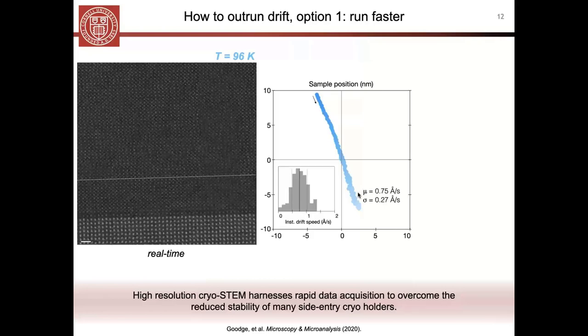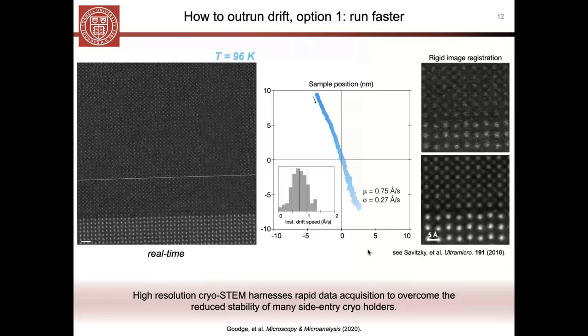Now, for very fast imaging techniques, or relatively fast imaging techniques like in particular high resolution TEM or high resolution STEM, one way around this drift is to acquire a series of very fast images - a stack of fast acquisitions - and then sum them together to produce a high signal-to-noise average that has overcome those position differences as a function of drift.